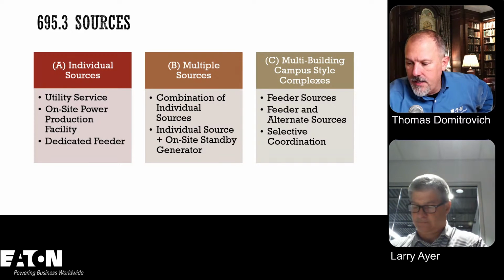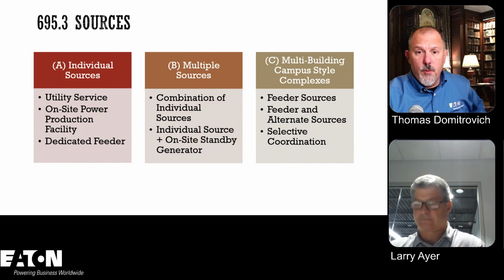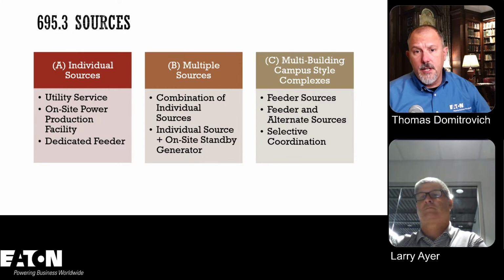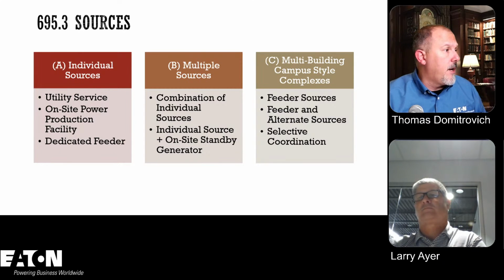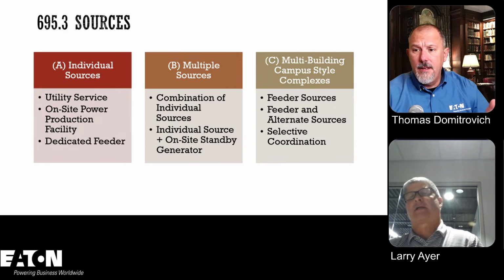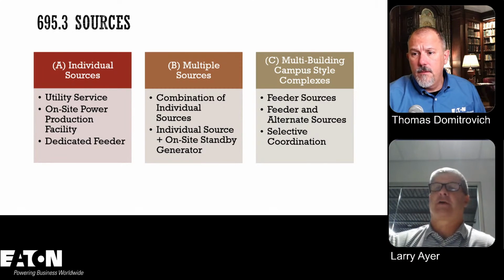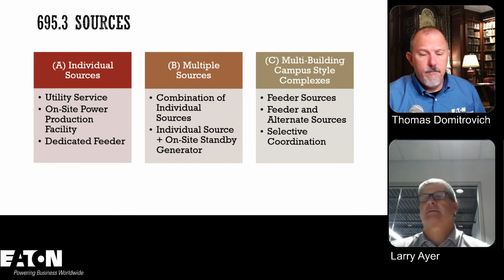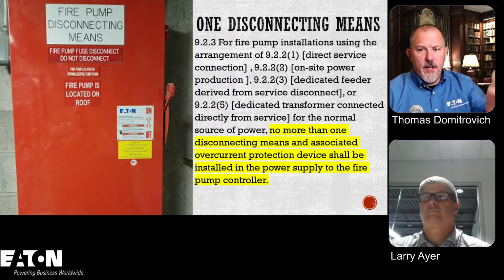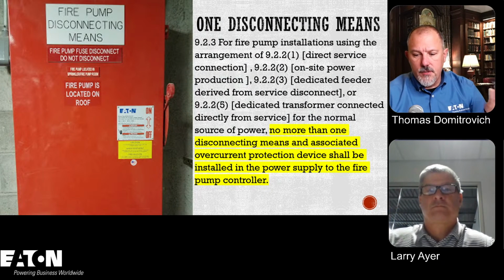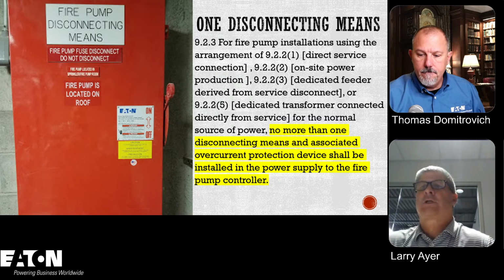It's all about reliability. That's the situation where you're going to have multiple overcurrent devices, so you have to make sure they're properly coordinated. Correct. Especially when you have feeders, you're going to have probably more than a couple of disconnects. But when you have a direct feed, you're coming off the service. There's nothing to coordinate. Correct.